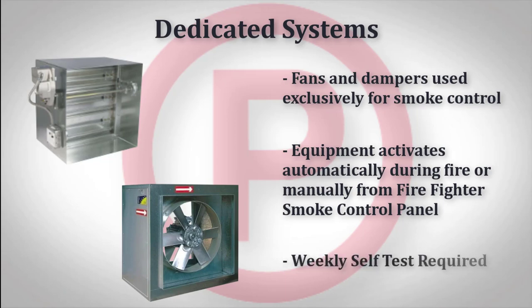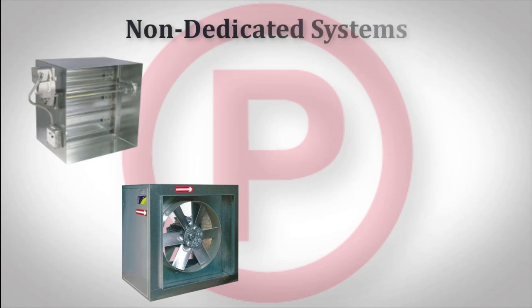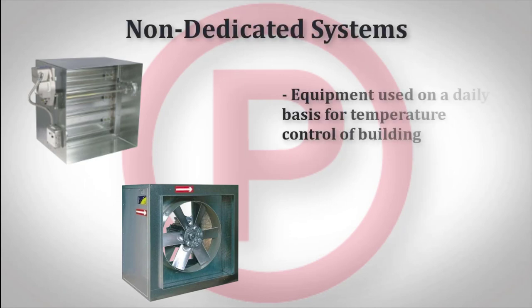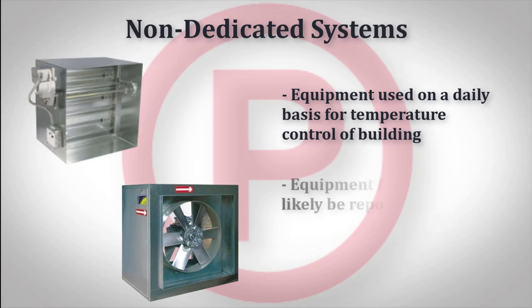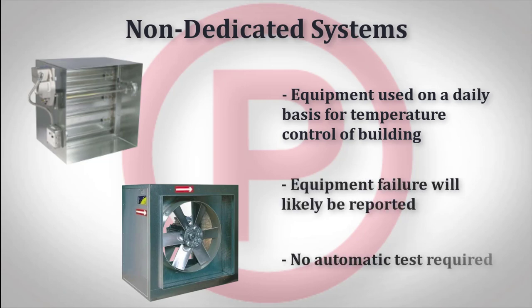A weekly self-test is required to assure it's operable. The second configuration is a non-dedicated system. In this type of system, fans, air handling units, and dampers are used on a daily basis for temperature control of a building. Since this equipment is used on a daily basis, it is considered more reliable and does not require a dedicated weekly test.